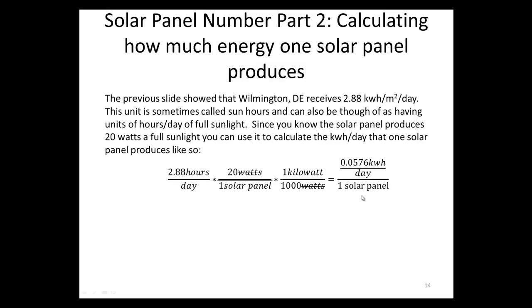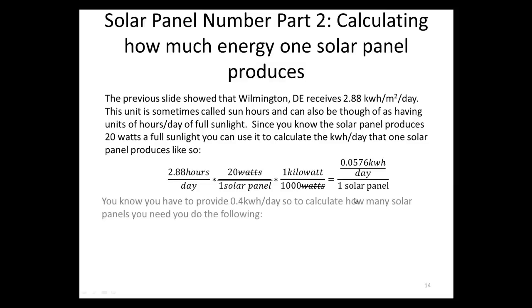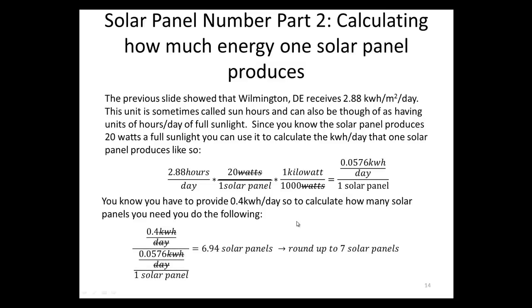We need to figure out how many solar panels are required to produce what we need. We have to provide 0.4 kilowatt hours per day, and each panel produces 0.0576 kilowatt hours per day. Dividing 0.4 by 0.0576 gives 6.94 solar panels. Since we can't have a fraction of a panel, we round up and need 7 solar panels.